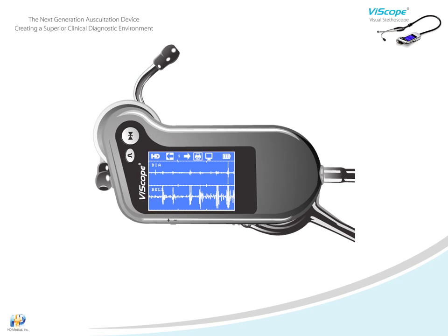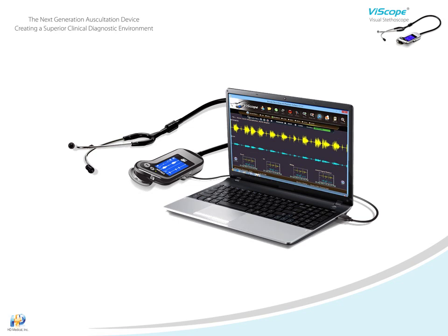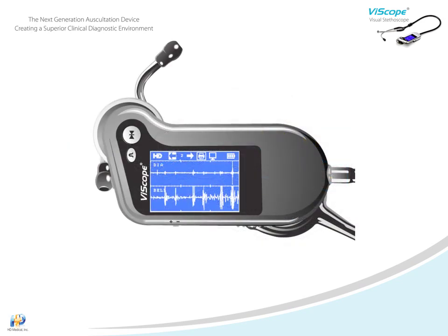Addressing the needs of today's evidence-based medical environment, one of the more salient features of the ViScope is the ability to save heart sound waveforms. This enables documentation of heart data which can be used for patient reporting and analysis, as well as information sharing or for use in teaching situations. Let's take a closer look at this important documentation capability. Each time a patient's waveforms are on display as a stationary trace, the option to save that record exists.